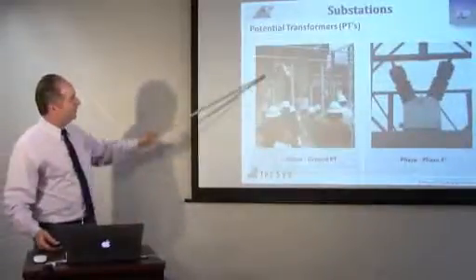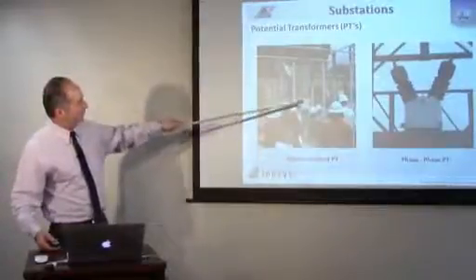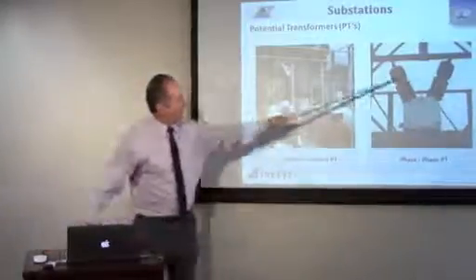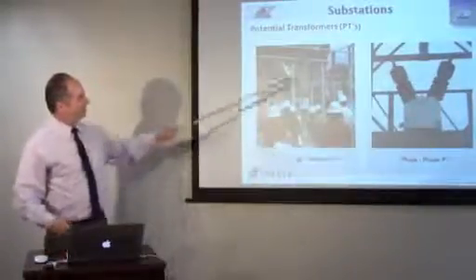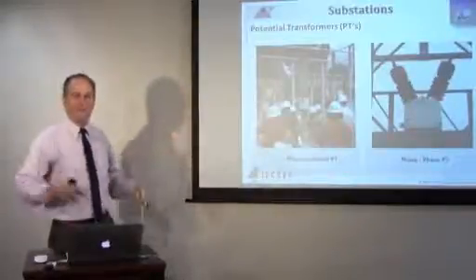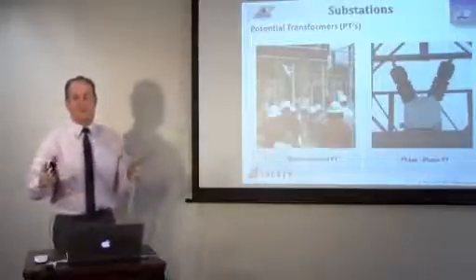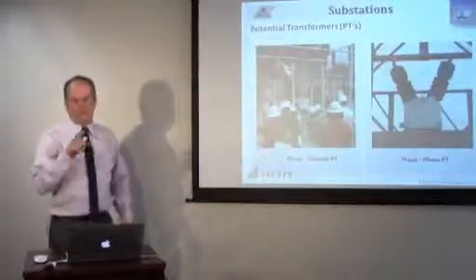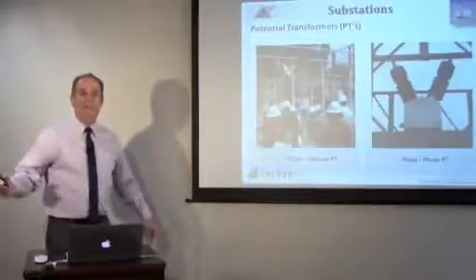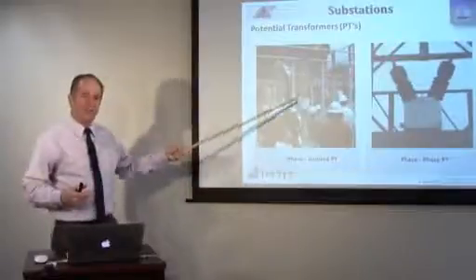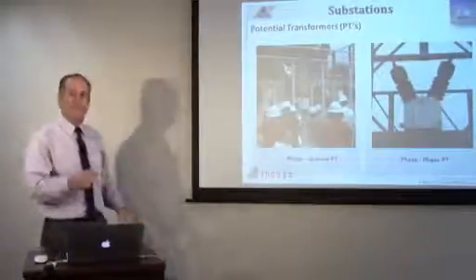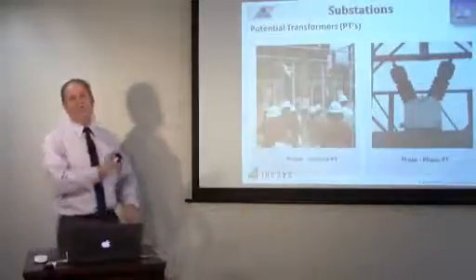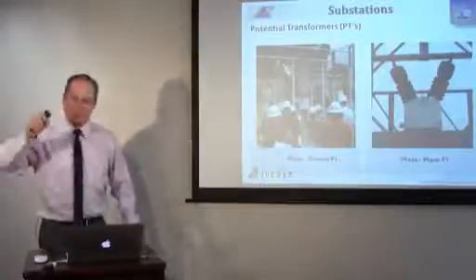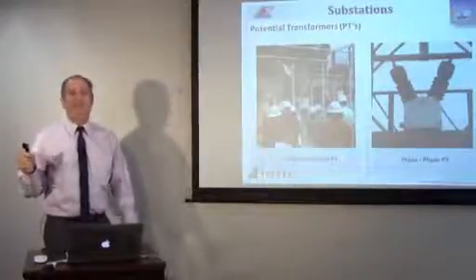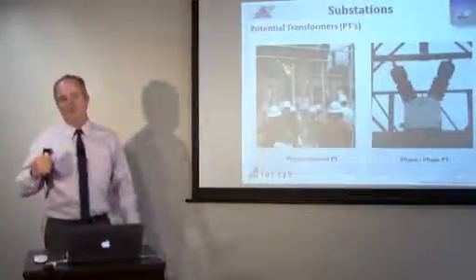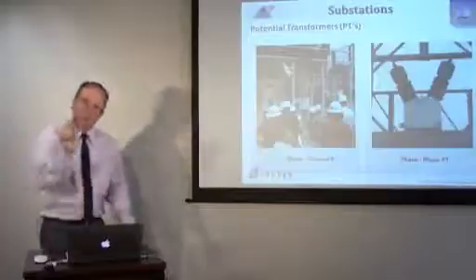Here are PTs. There are 3 PTs here, 1 for each phase. This is an older type wire wound, and this is a phase-to-phase PT. And single phase PTs line to ground measure bus voltage. So when you're in System Control Center and you're looking at a one-line diagram and it says bus voltage is 236 kV, where does that information come from? It comes from a PT like this out in the substation that's actually measuring the voltage, dropping it down to something like 120 volts, so there's a turns ratio. That goes into a transducer, which further reduces that ratio down to something a computer can recognize. And then that information is sent to System Control, and the System Control computer multiplies those 2 scale factors and gives you the real number back on the screen.